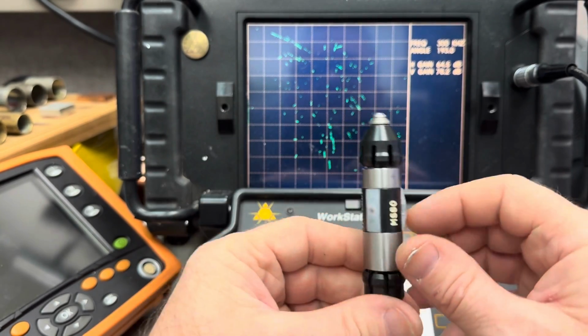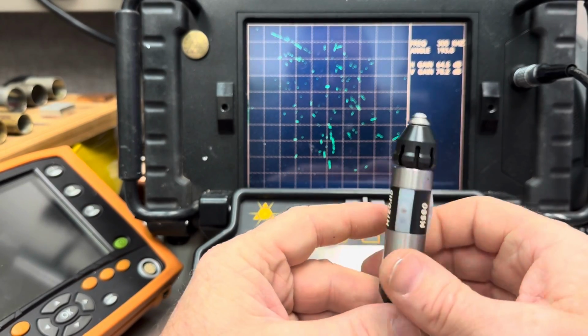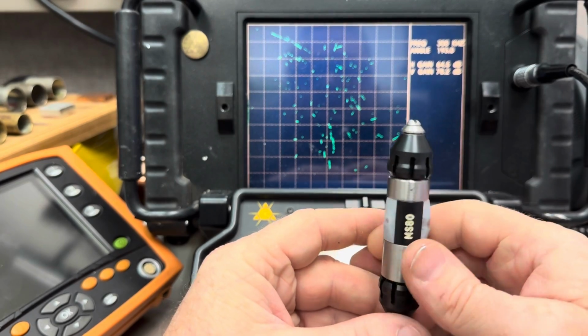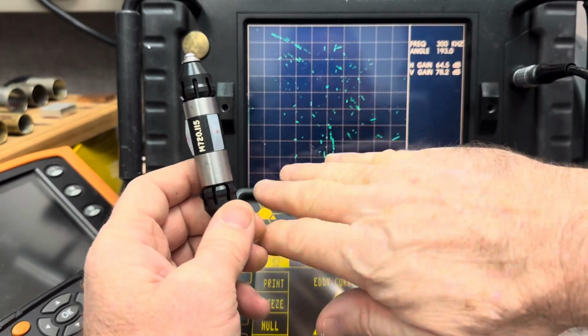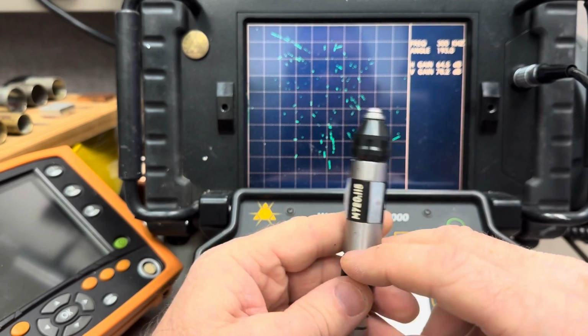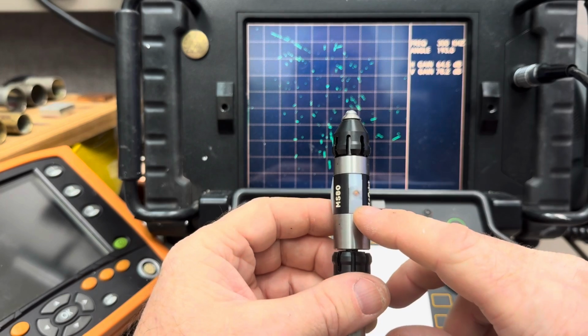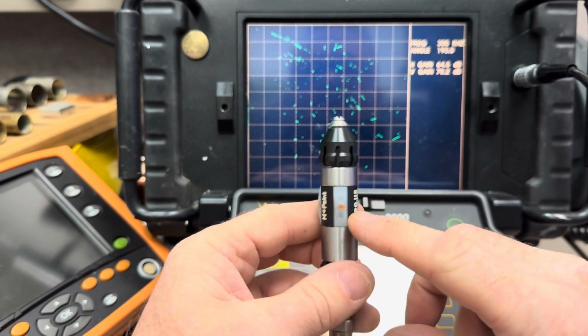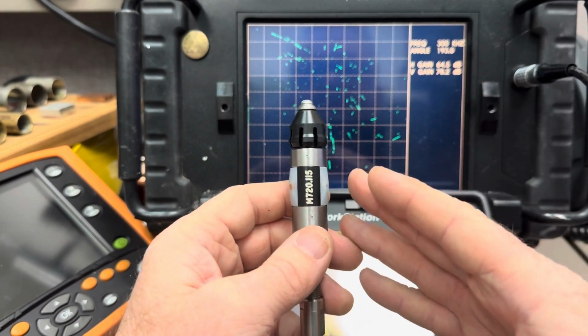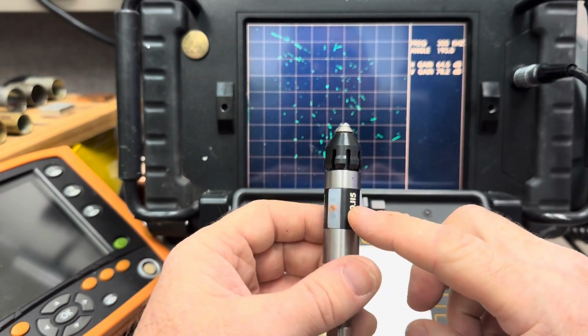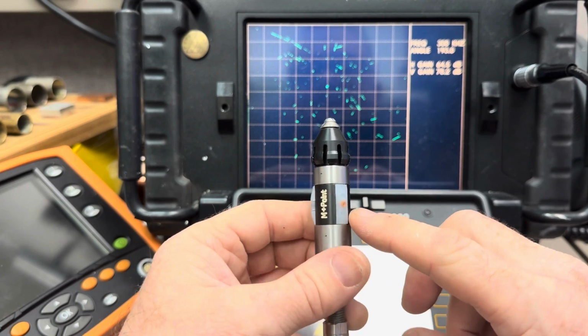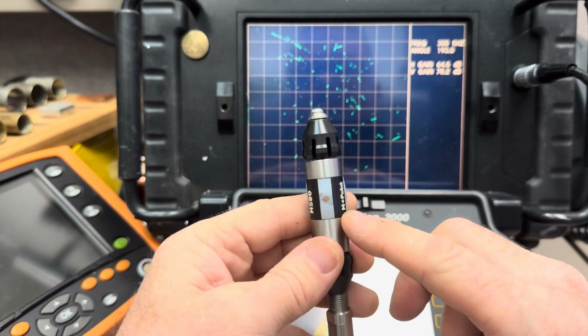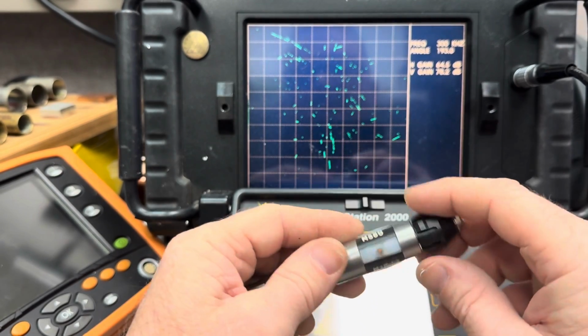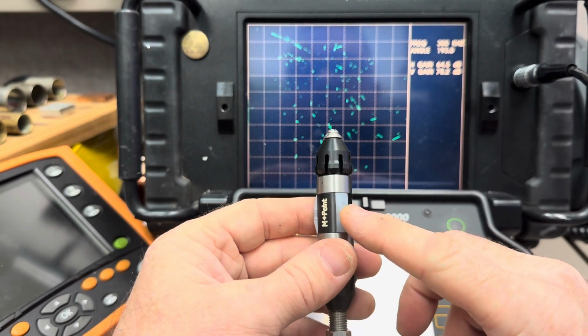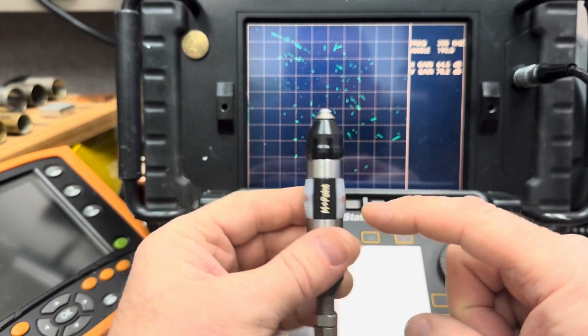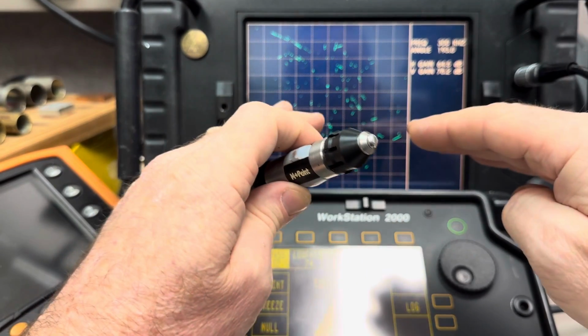And as this thing spins at 1500 RPMs or whatever it spins at, you're collecting data from all three coils. And then when you do a terrain plot, the nice cool 3D terrain plot with all the colors like you see with the rotating coils and array probes, the data from each one of these coils can be offset by 120 degrees. So as you're flipping through the different channels, you'll see the flaw shift based on what coil sees it. So to overcome that offset, there is a feature in your software called data slewing. So you just take channel 1, let's say it's the plus point coil, and then if the 080 or the 115 pancake is 120 degrees away, which it is on the probe, you can just adjust your data so it lines up.